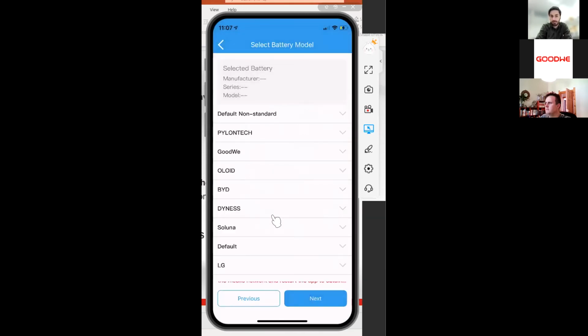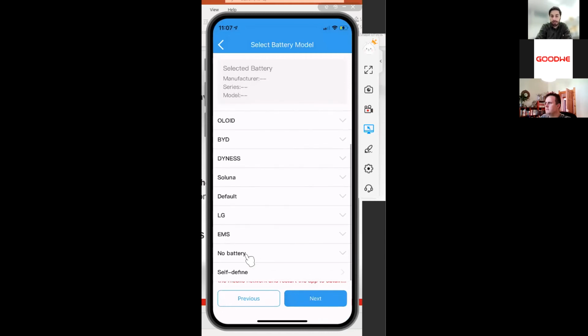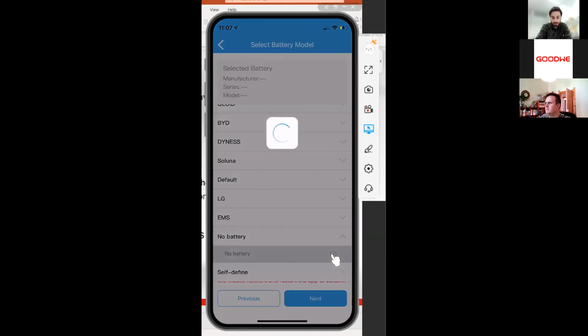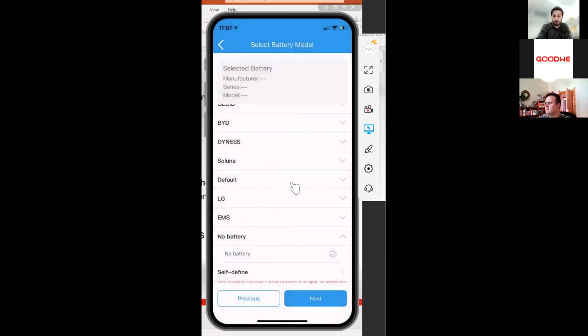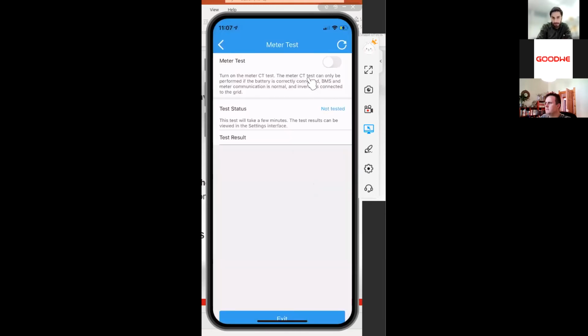And then we now need to select the specific battery. In this case, we do not have any battery, so we then select no battery. And then sometimes it even says unsuccessfully, but that's also okay because we don't have any battery. Battery communication failed. Yes, we do not have one, so we don't care. We then go to the meter test, and here we can do a meter test to check if we connected the CTs correctly. However, now I haven't connected.